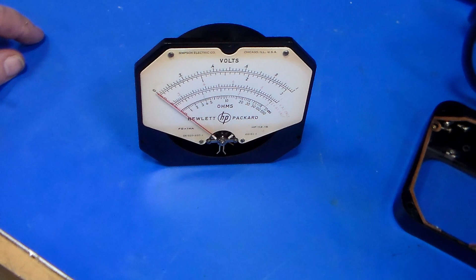After letting the HP 14B warm up for about 15 minutes or so that it can thermally stabilise, you should be able to adjust the zero setting to give zero on the display, and then actually be able to switch between positive DC and negative DC without any significant change to the meter needle. And that's what we've got here.